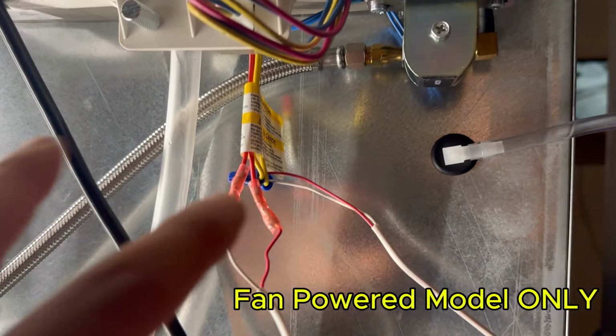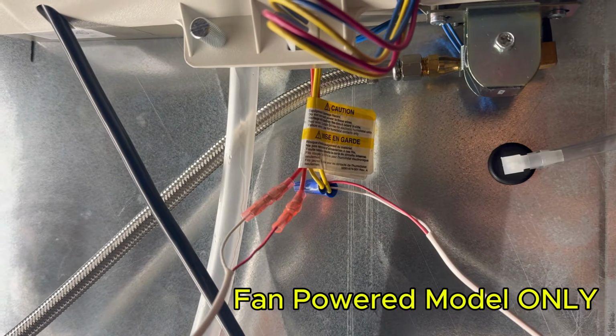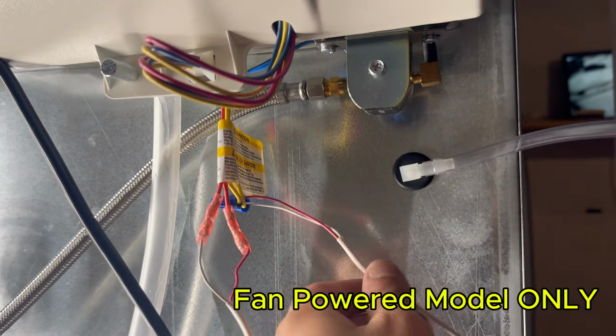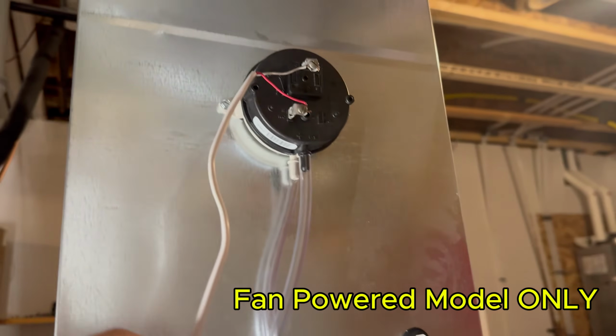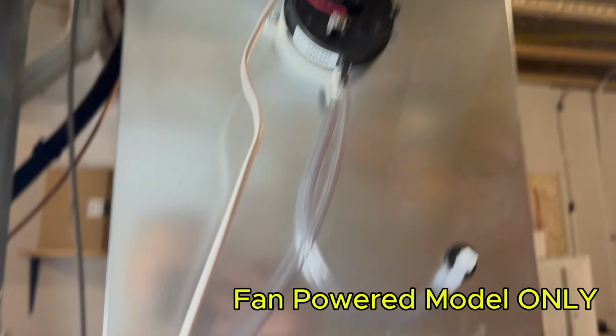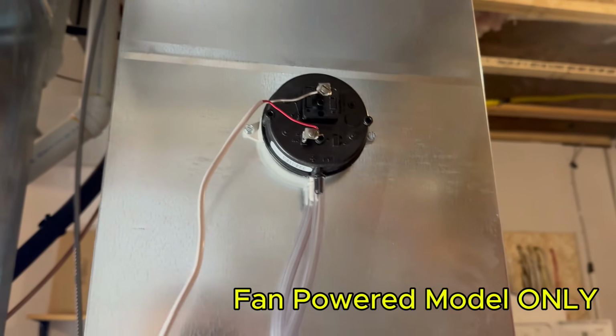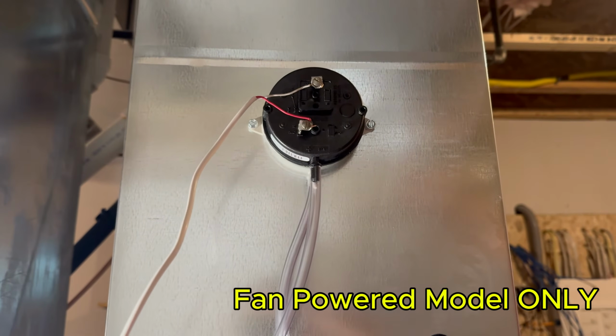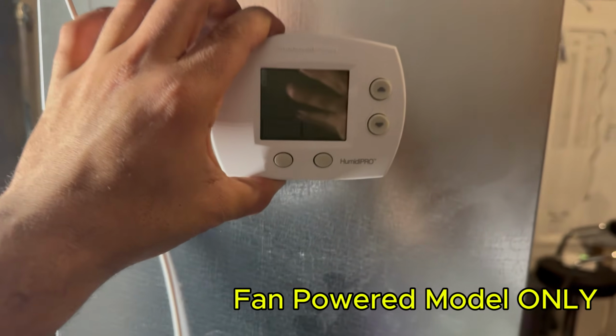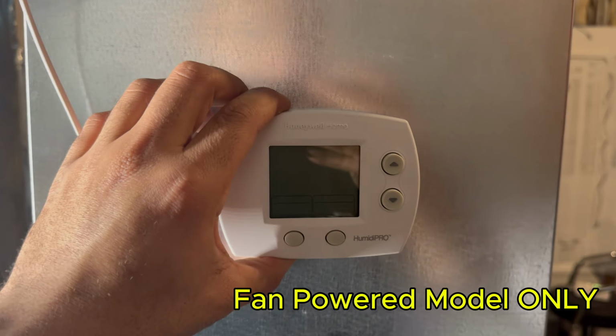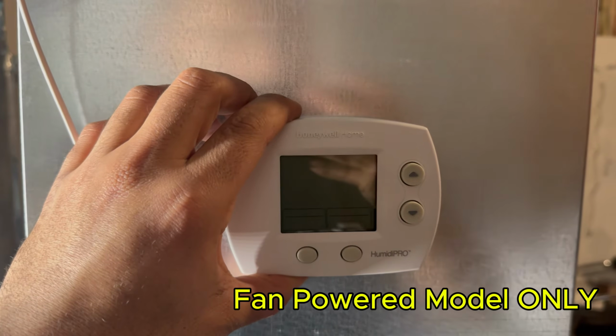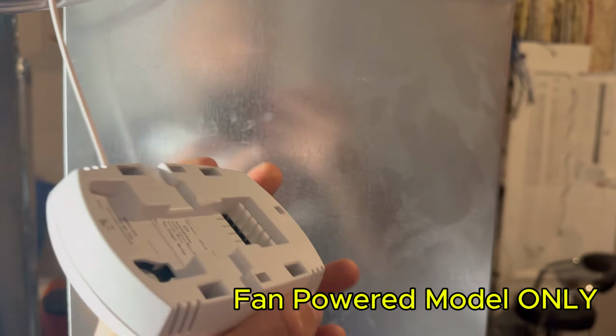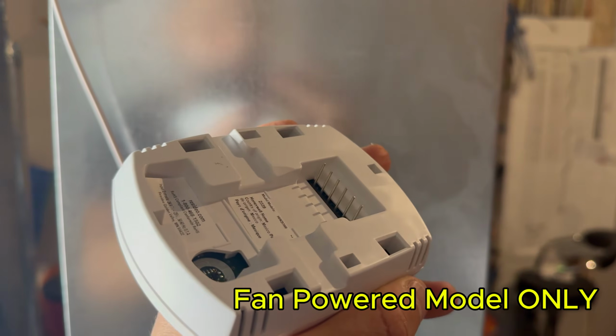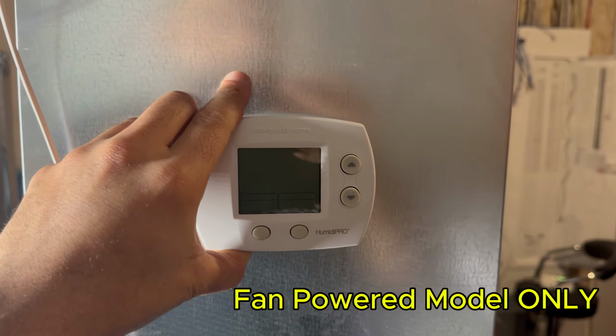So far we have 2 low voltage wires running from the red and 2 low voltage wires running from the yellow. The third strand of wiring is coming from the pressure switch. 2 of them, leave the other end disconnected. And now I'll show you how to bridge them all together using the digital humidistat. Assuming you followed the instructions and you've mounted your digital humidistat to the return side of your ductwork, again, the package comes with a template, and this one is a little bit different. You drill a small hole and insert a reading module.